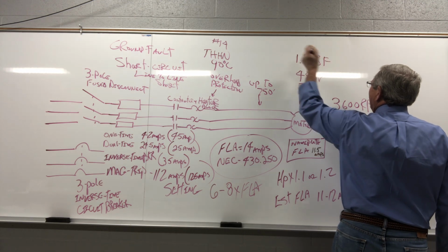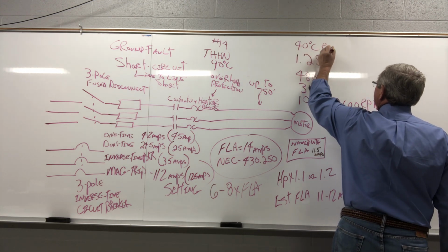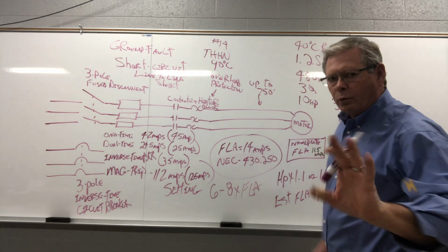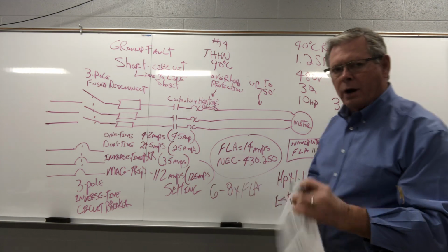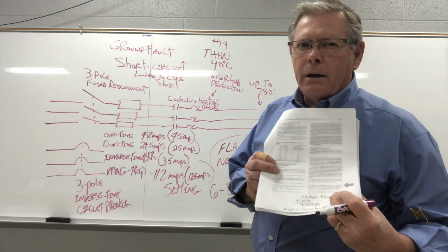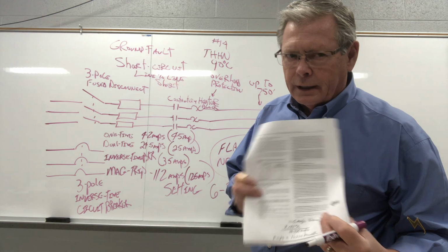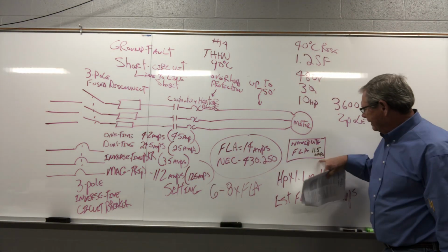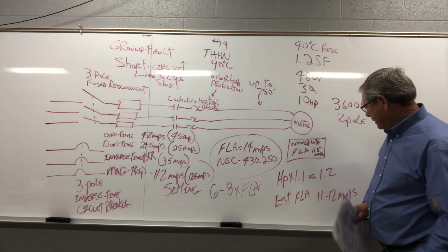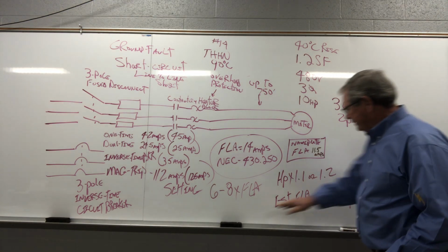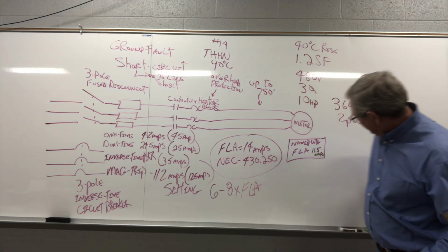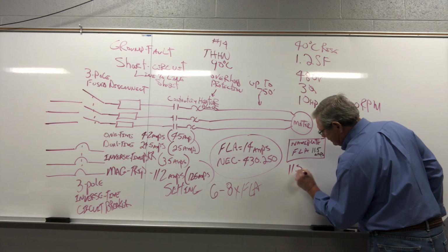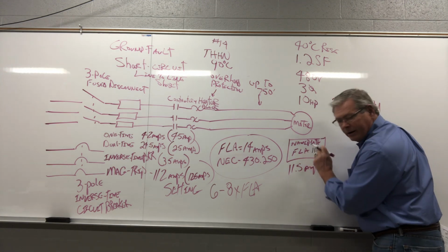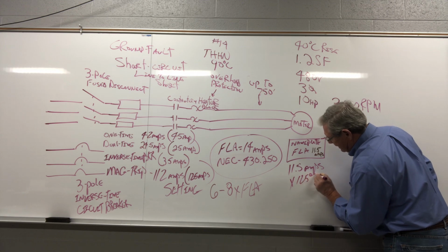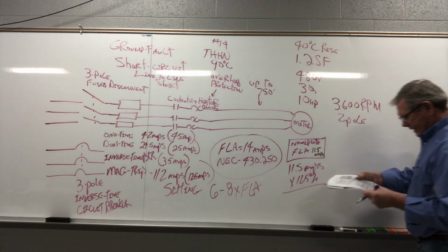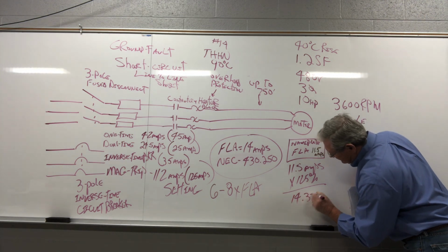1.2 SF, and it's a 40 degrees C rise over ambient. Either one of those two, and we go to 125% of our full load current, okay? So, if we take 11.5 here and multiply it, I'm going to erase this here so we can have a little room. If we take 11.5, now that's nameplate current, times 125%, we get 14.375 amps.